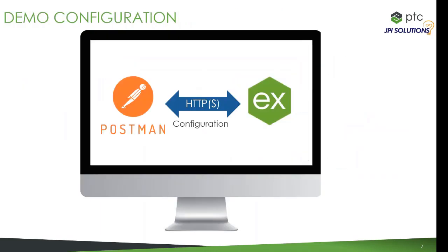So to show folks how it works from a very basic perspective, we have a demo. What we'll do in this demo is illustrate one of the first things that customers want to do when they open any OPC server or connectivity solution, which is to create a connection to a device. In KepServerEX, that requires creating a channel to that device, identifying the device itself, and identifying the tags to connect to in that device. So we'll do a demo of creating a channel, device, and tag in KepServerEX using the configuration API.